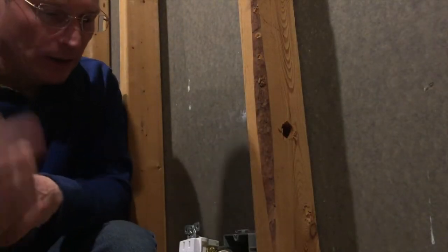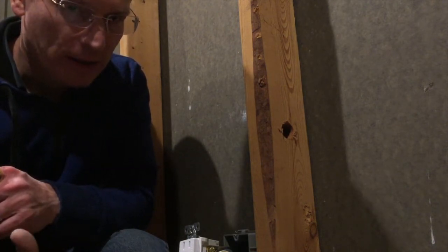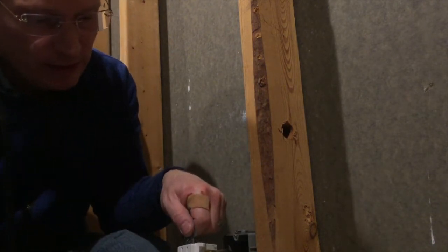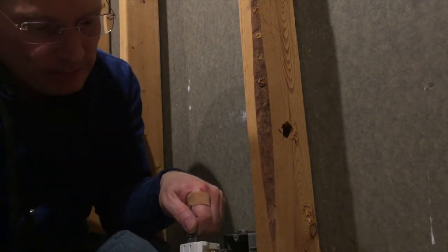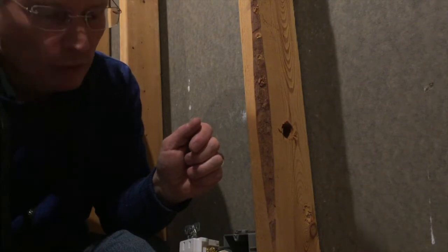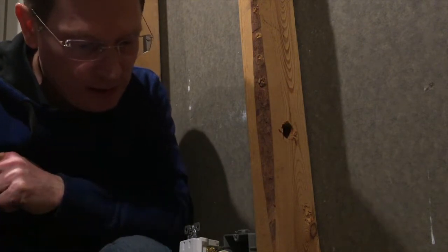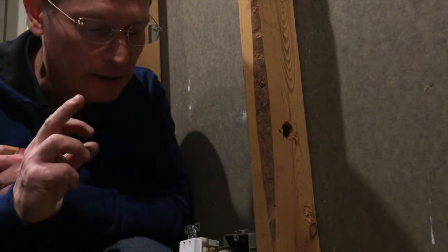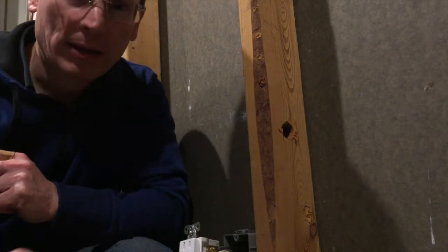Turn the electricity back on. I disconnected the line side of the final 7th outlet. And let's see if it's the wire or if it's the outlet. Okay. And I am shocked, both figuratively and literally. It's a problem with the outlet.